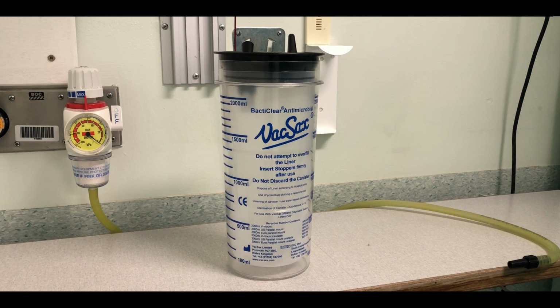And welcome to the Vacsax Advanced Liner Medical Devices training. By the end of this training, the objectives are that the user will be able to use the liner appropriate for its intended use, demonstrate how to check for damage, wear and faults, understand the limitations and contraindications of the liner and canister, be aware of the relevant accessories available, be able to demonstrate how to safely set up the liner, be able to demonstrate how to check that the liner is working correctly, be able to demonstrate how to dispose of the used liner and associated accessories, be able to demonstrate how to clean and decontaminate the Vacsax liner, and understand the actions to take if there's an error or failure of the device.